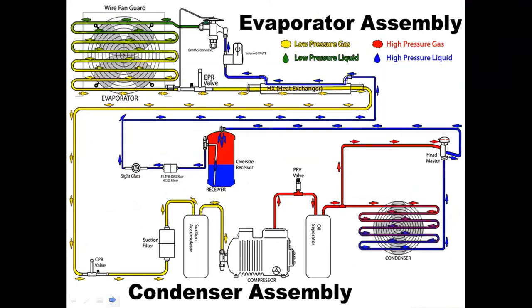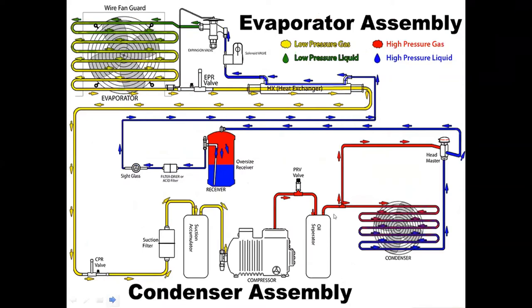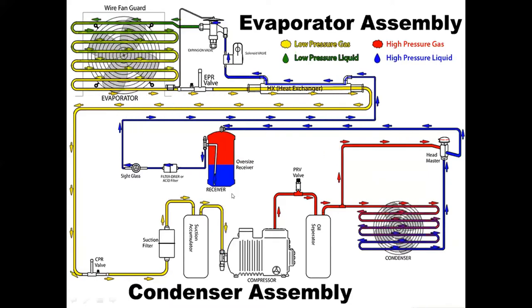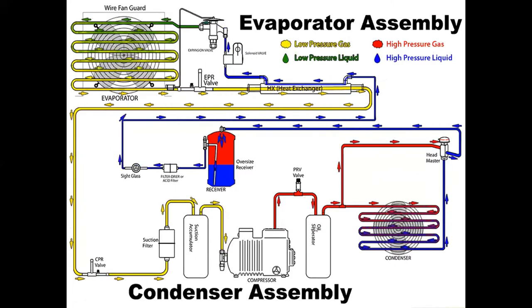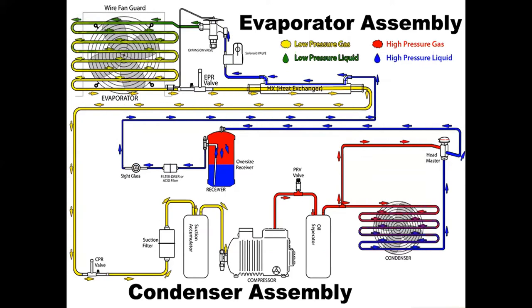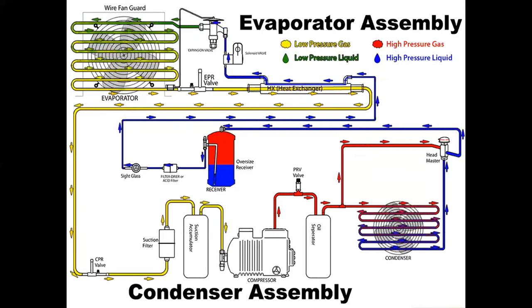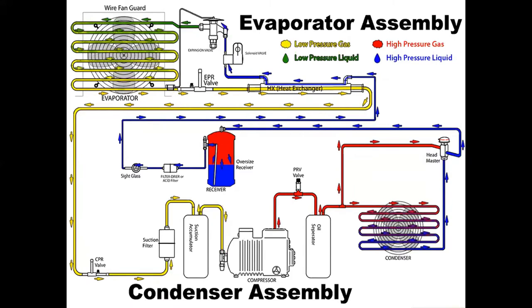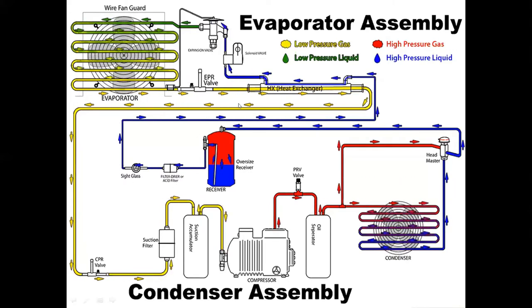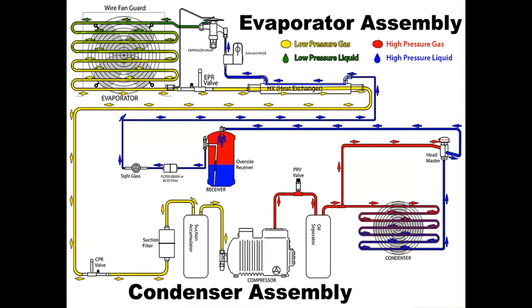This is the refrigeration cycle where you can see it has many parts. The major parts are the evaporator, condenser, compressor, and expansion valve — these four are the major parts without which no refrigeration cycle can work. But apart from these, there are other components like the oil separator, which prevents carrier oil from reaching refrigeration equipment, and the suction accumulator, which prevents liquid from reaching the compressor. All parts — receiver, sight glass — play a vital role.